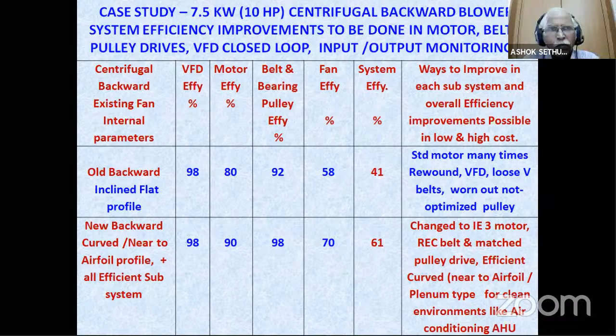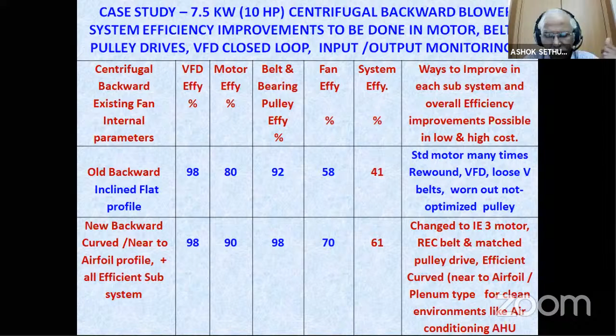Now, the system efficiency is the multiplication of the efficiency of all the subsystems. Let us say this blower has a system efficiency of 40%. You just multiply each and everything. See, motor efficiency, VFD efficiency, belt and bearing efficiency, and the fan efficiency: 98, 80, 92, 58. Automatically, only 40% is delivered at the output. So, if we have to improve the system efficiency, you have to improve the efficiency of each subsystem. This is the crux of energy conservation and audit, what we do in the industry. So we have improved the impeller from 58 to 70, and automatically from 40% it has jumped to 60%. And the industry is happy with almost 20% energy efficiency improvement for a given blower.